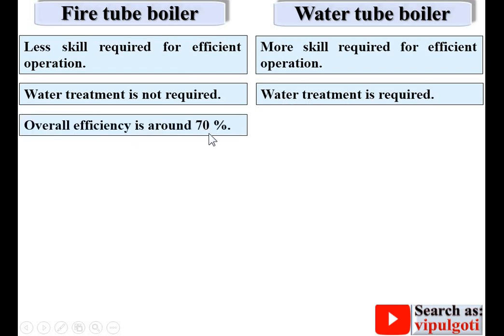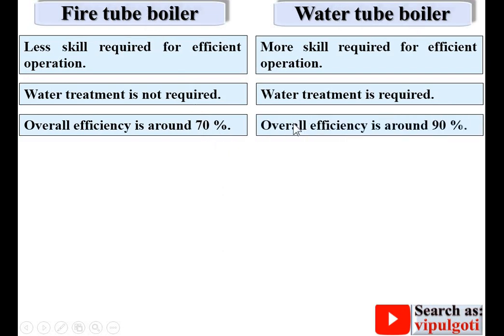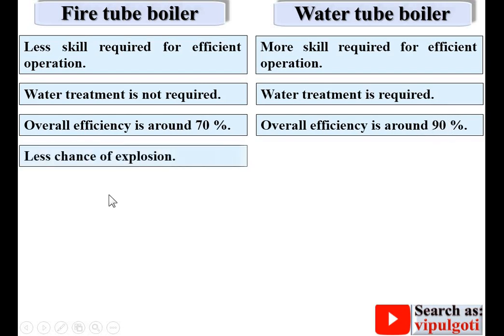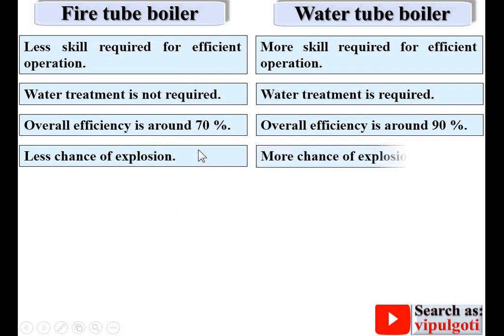Overall efficiency is around 70% in case of a fire tube boiler, whereas in case of a water tube boiler efficiency is up to 90%, which is why it is generally suitable for large power plants. There is less chance of explosion in fire tube boilers because pressure is up to 25 bar, whereas there are more chances of explosion in water tube boilers because pressure is up to 125 bar.